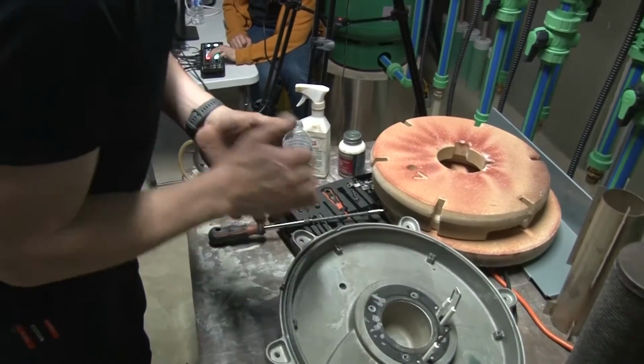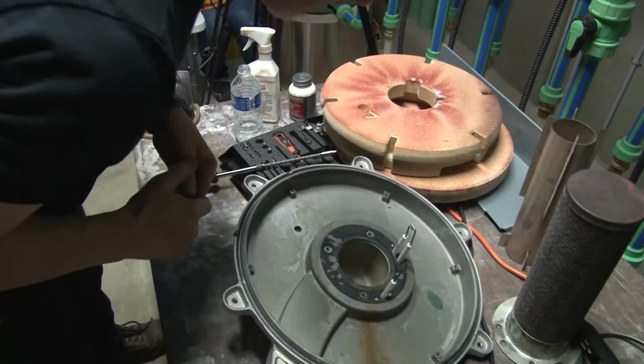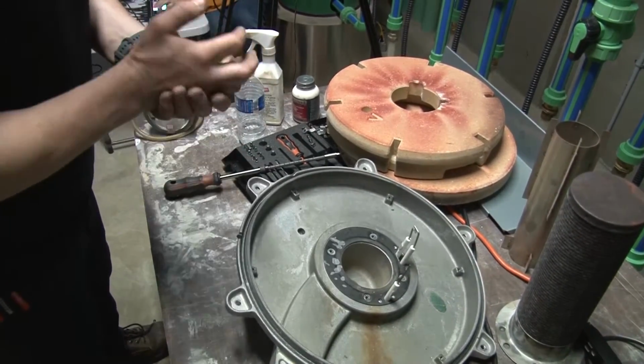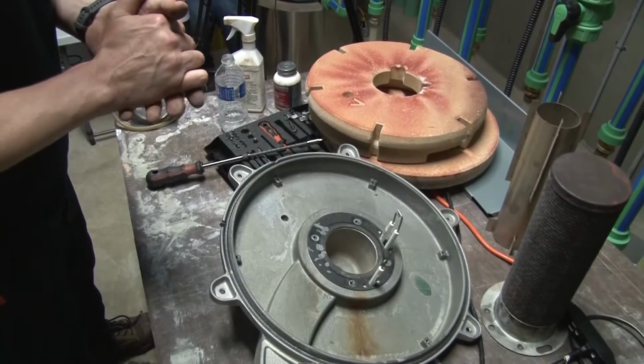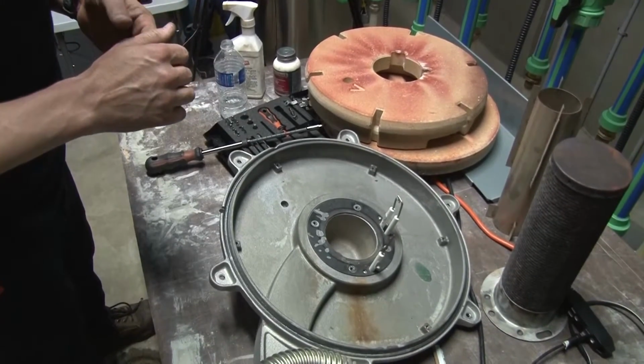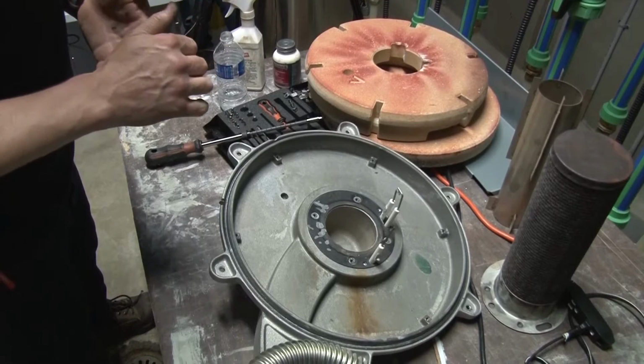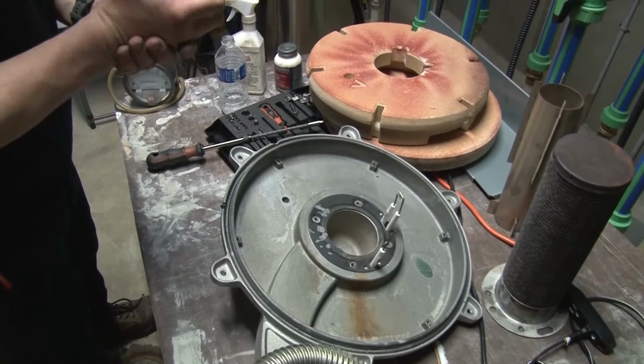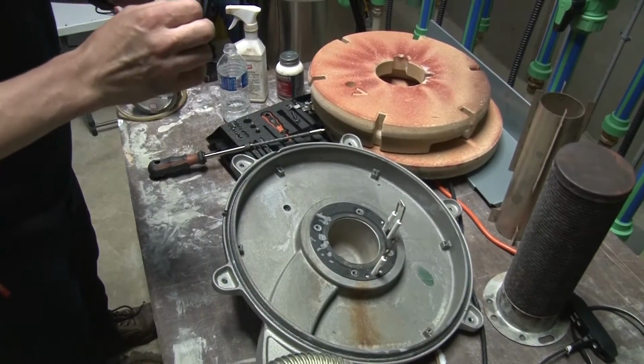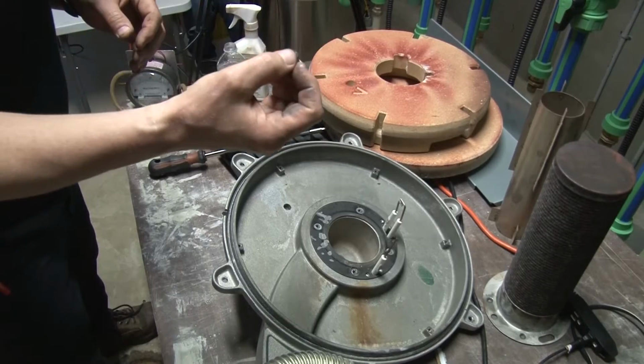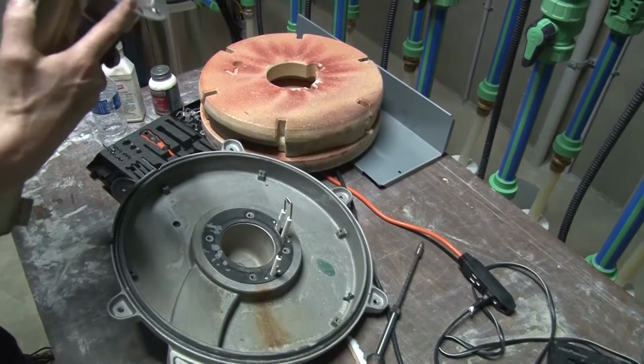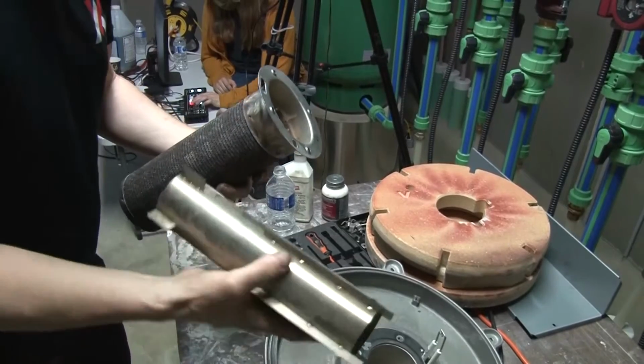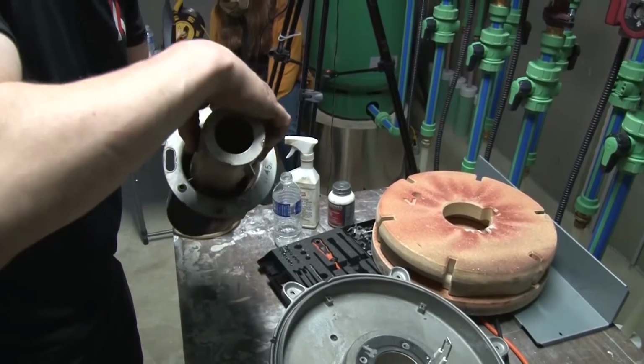And again, there's the refractory or the gasket we're talking about. And we would be looking for things like breakage or something like that in the gasket. That could be a problem. If we see a break, then we would basically want to replace the gasket. If we didn't have a replacement, we'd want to get one on order. We're looking for this little flange area to be nice and flat. This only goes in one way.